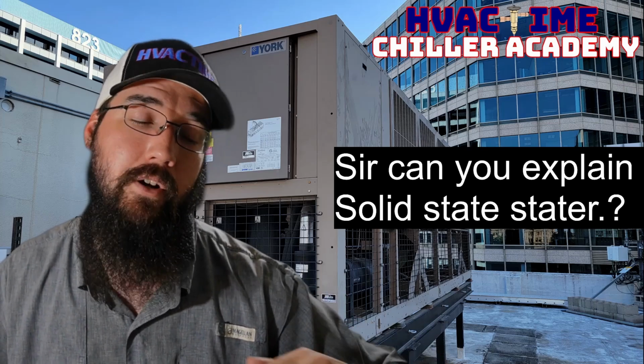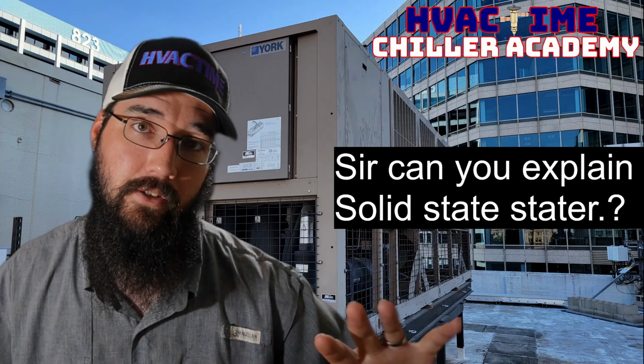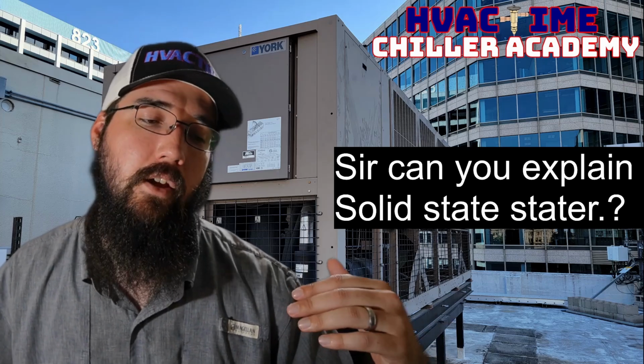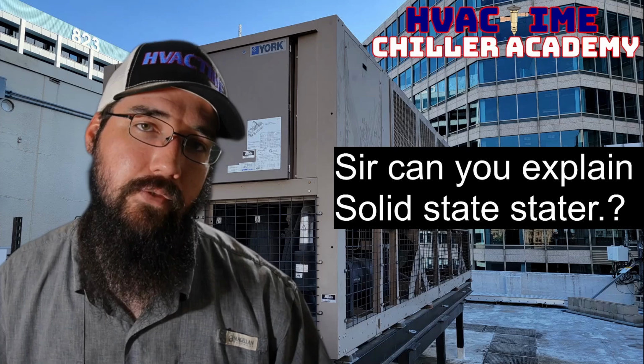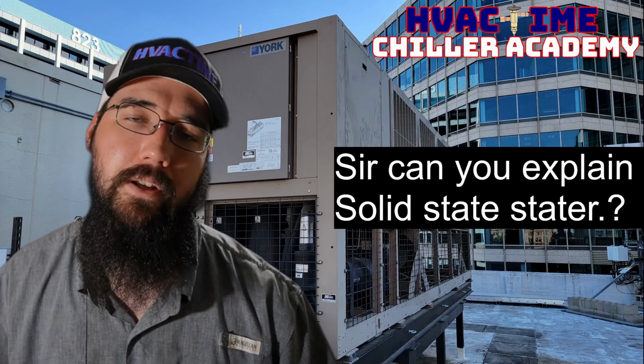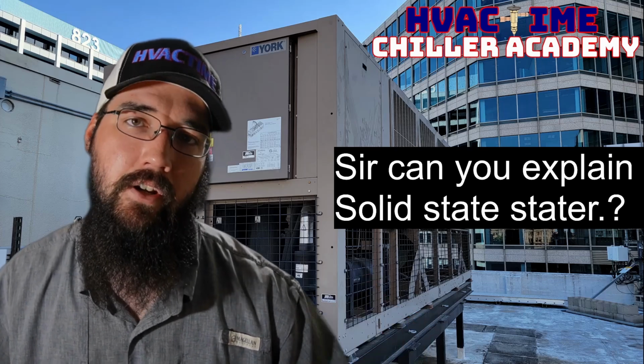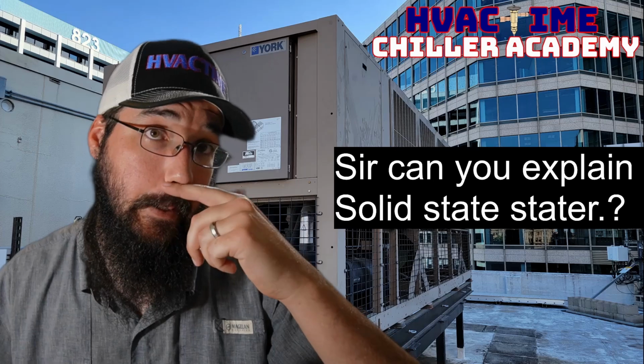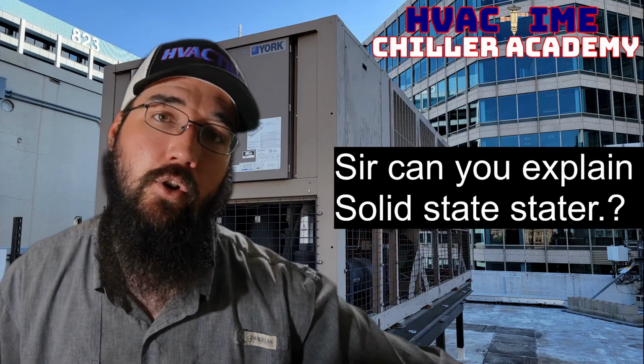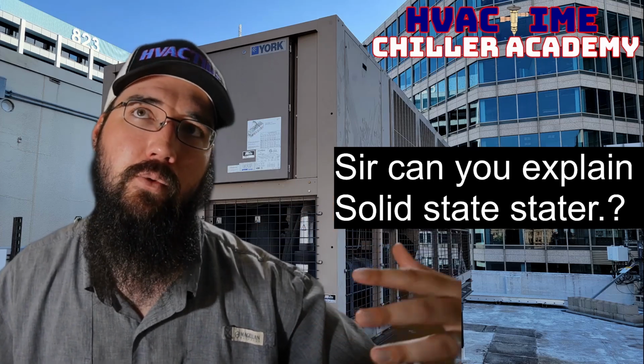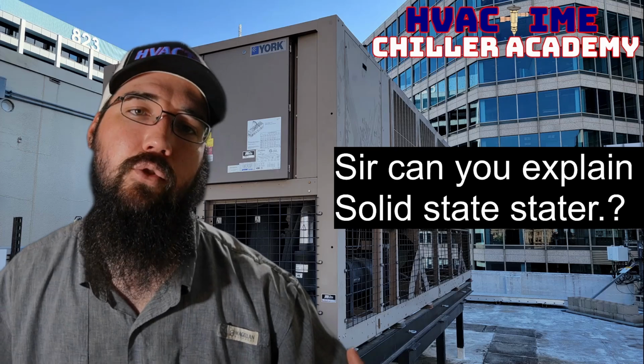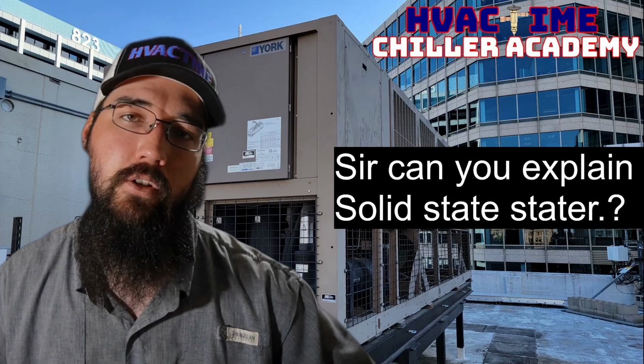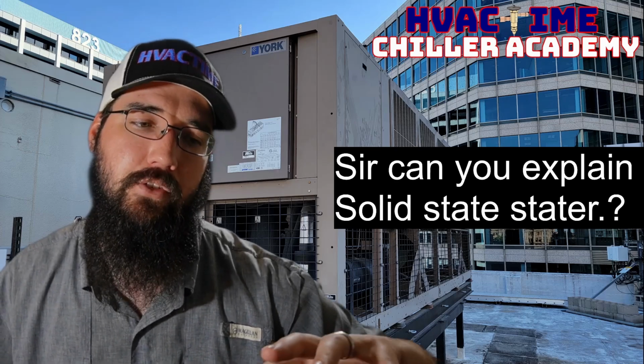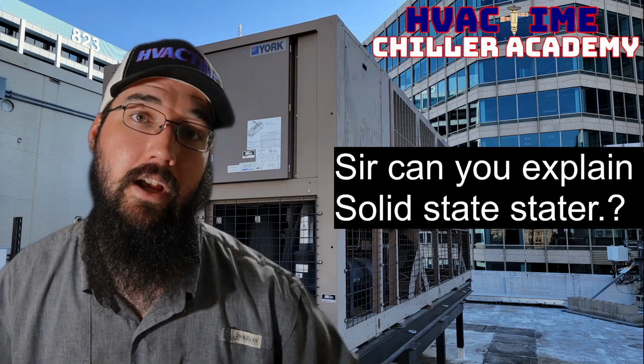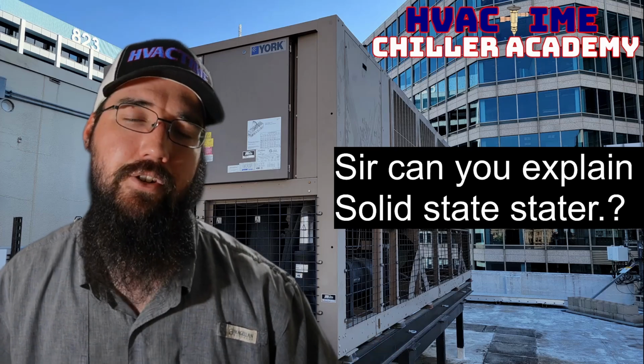straight to the motor, and it better hang on, and it's going to take off and go. So that's really difficult on the motor itself. That puts a lot of stress on it. You have a really high peak in the starting current, right? And it also costs a lot of money to do that once you get to a large enough scale, because starting a large motor like that across line takes a lot of energy.